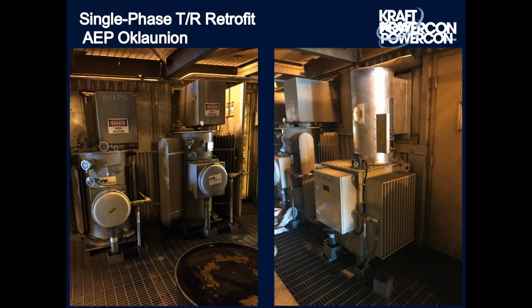And so here we're able to put the junction box and have the conduit connections in the same place using the same cable, which is important. When you start talking 500 MCM cable, that stuff is difficult to work with. So if you don't have to cut it, re-terminate it, or change it, that's a big benefit. This slid directly into the side wall, and instead of an internal ground switch, it's got an external ground switch. So the plant maintenance did this themselves as simply as they did with a spare TR set from GE.